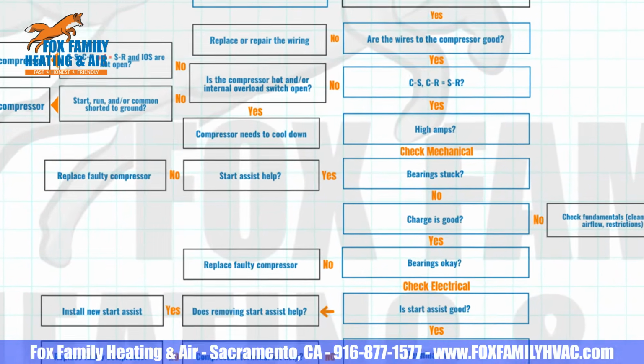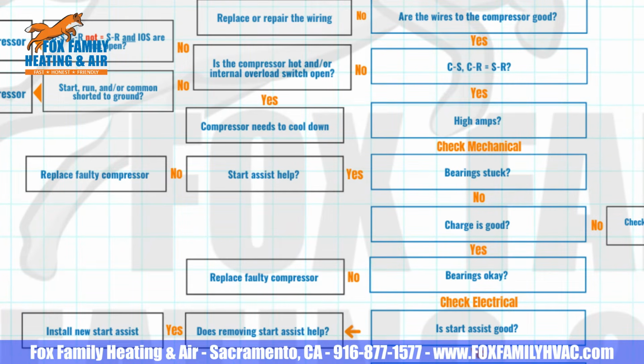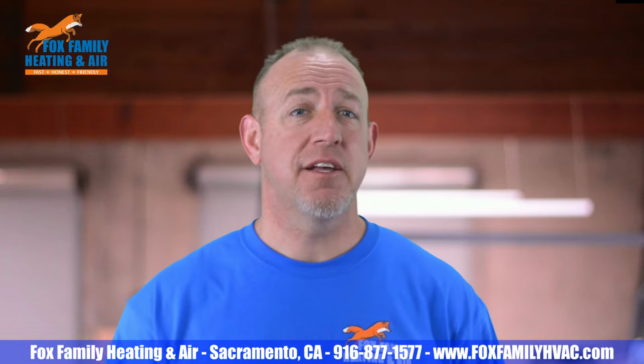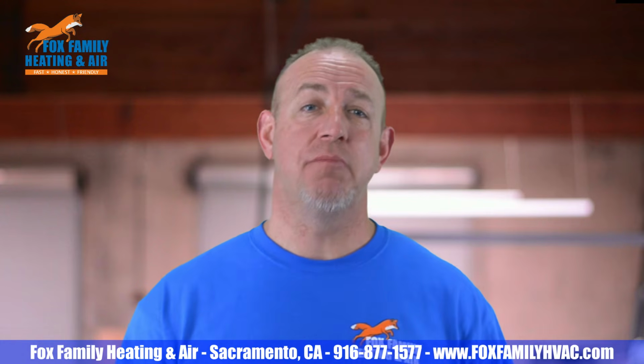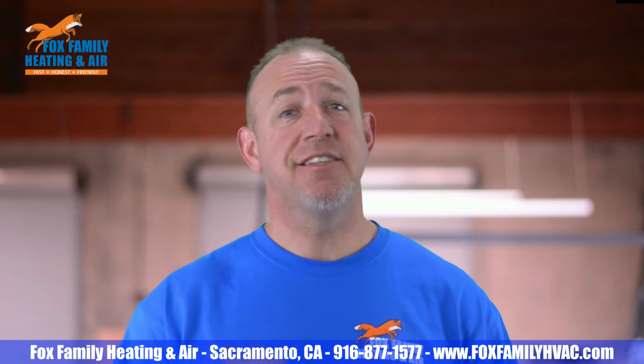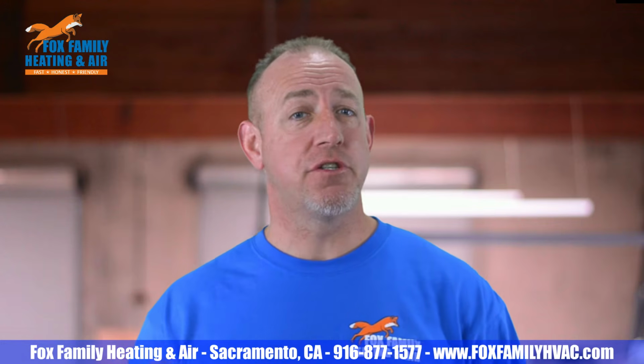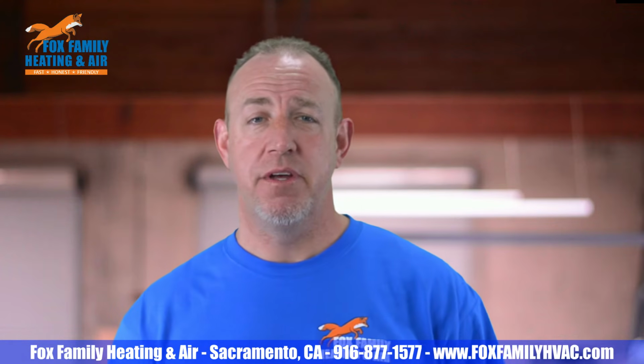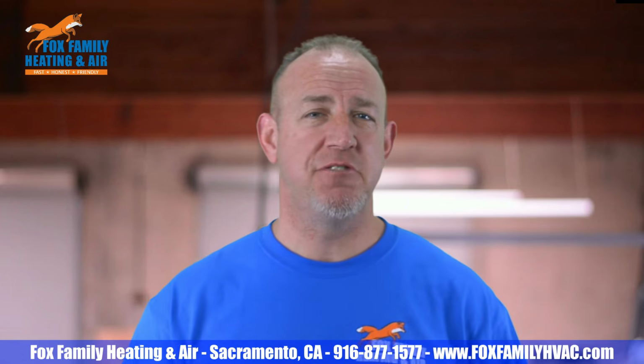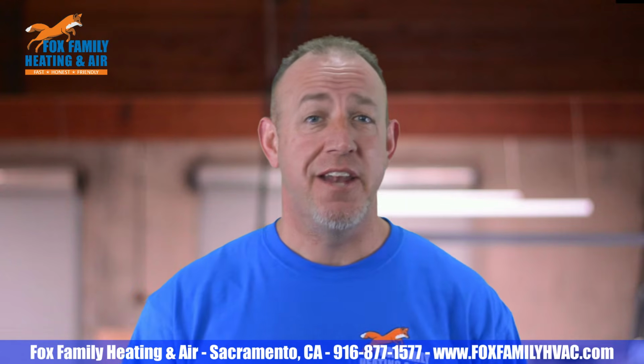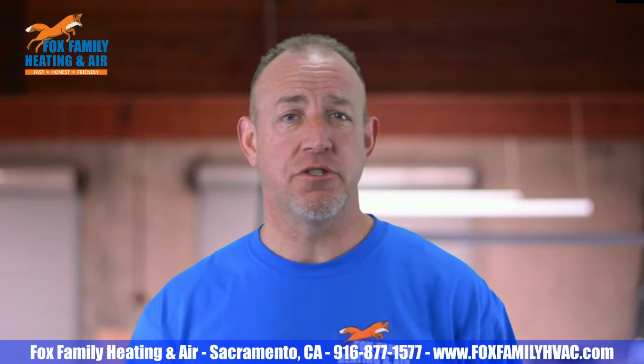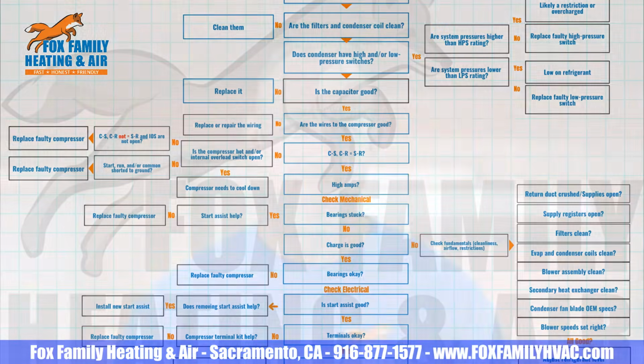Is the compressor stuck? Throw a start kit on it to give it that kick that it might need to get going. If that works, let the customer know that their compressor is on borrowed time. I see this happen on older systems first startup of the year after a long winter. The bearings seize up sometimes and just need a little kickstart. A nod to those of you who don't believe compressors should be outfitted with a start kit.